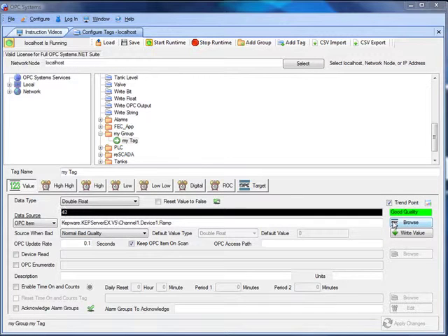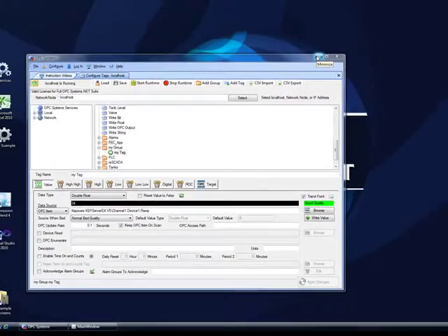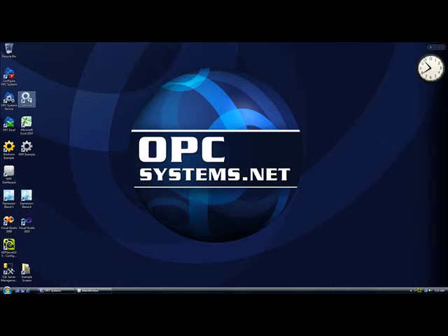If while browsing your OPC item, or if you're getting bad data quality from the OPC server, one of the common resolutions is to set the OPC system's data service logon to your local user account. Some OPC servers do not run as a Windows service. The Kepware OPC server that we just connected to runs as a Windows service, so most likely you'll be able to connect to it with a system account. But some OPC servers run as a desktop account, and so your operating system needs to have the privilege to be able to send values back from the OPC server to the OPC client that by default runs under the system account as a Windows service.